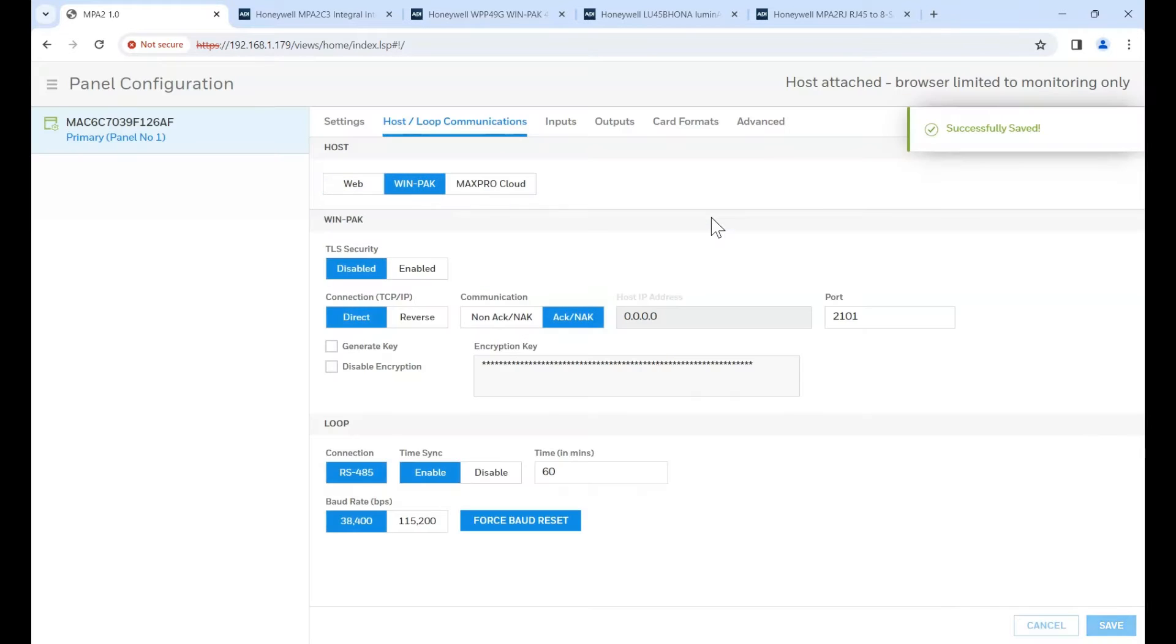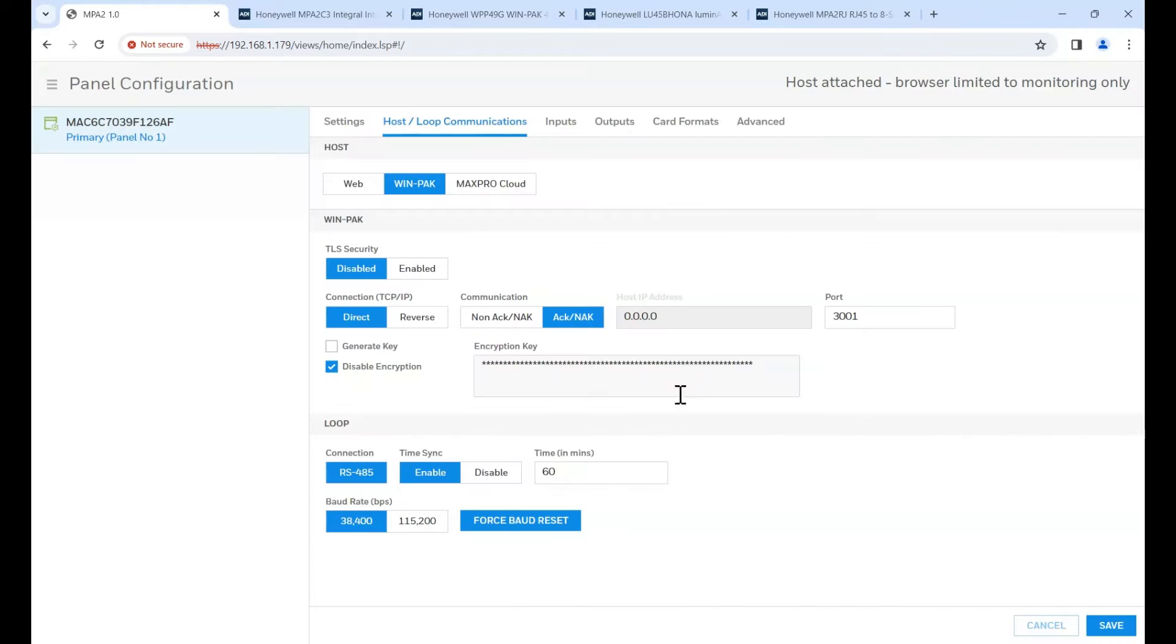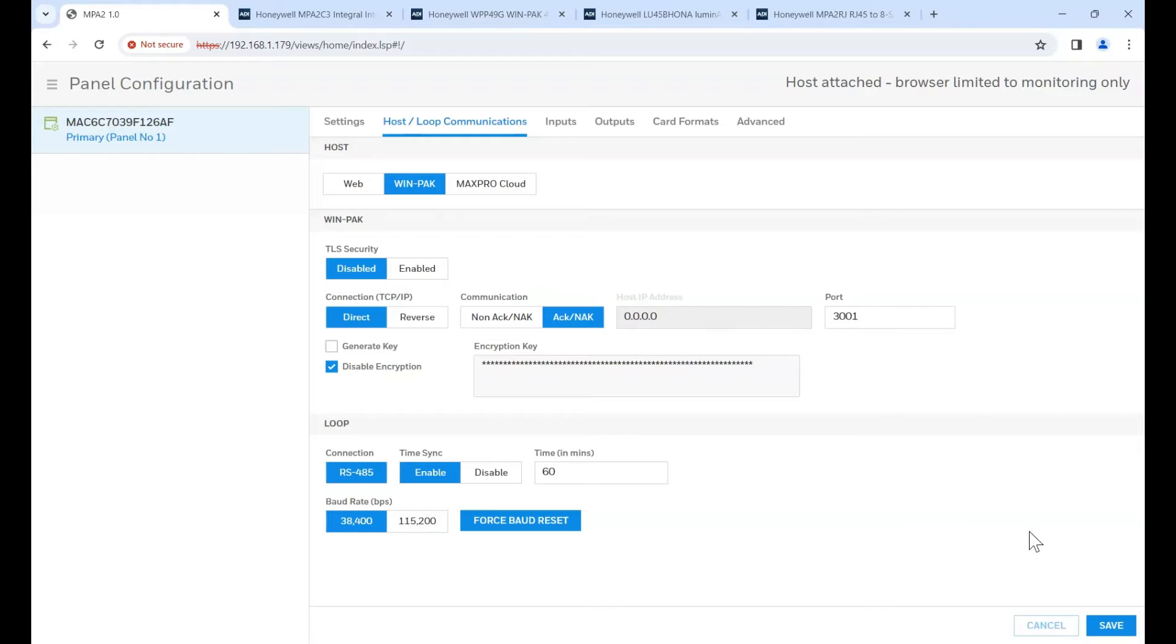Save that change. Okay. Everything's okay there. Disable encryption. Okay. You can see now it's changed its port to 3001. That's the standard port to use on Winpak. Save those changes. And that's the controller configured for Winpak.